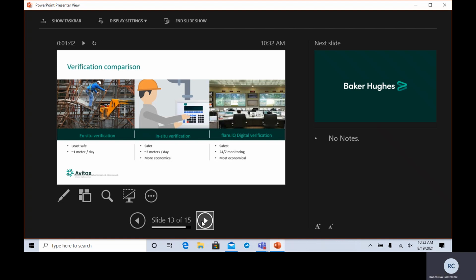The service team loves it, the service group. For me, the most important part is if you have a process upset, let's say you run 200 feet per second through your flare line, and everything's come back to normal, everything's fine. You're not due for your verification for 6 months. You're not going to call Panametrics up and say, hey, can you send somebody out just to make sure this thing's working right? You're not going to do that. But what digital verification allows is for you to do a verification on your own, on demand, with just phone support.